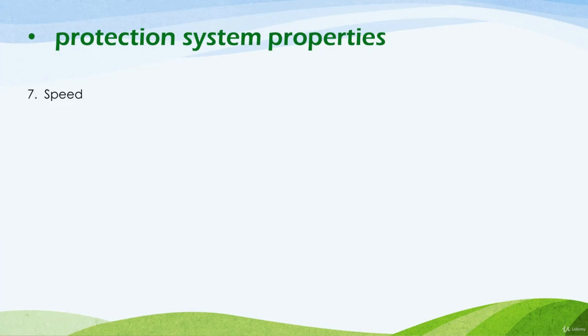Now the seventh property of the protection system is the speed of the protection device, and the speed means how fast the protective device breaks the circuit. As we learned before, the protection system needs a specific time to recognize the fault and break the circuit. So this time consumed specifies how fast the protection system is, or the speed needed to break the fault. The faster the protection system is, the more effective it will be, as it lets the full current stay in the circuit for less time.